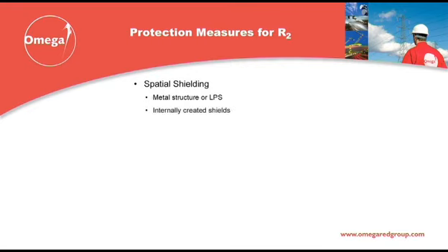Furthermore, in zones further into the structure, LPZ2 — an internal server room for example — if walls are constructed of metal studding or other conductive material and those are appropriately earthed, the LEMP effect may be further attenuated by virtue of these potentially inherent internal shields.